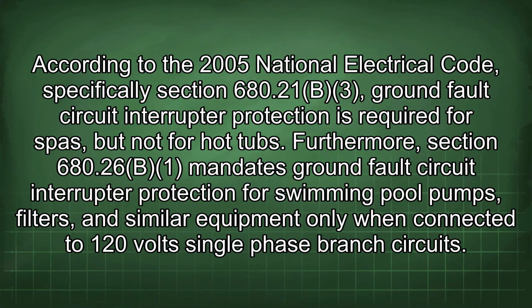According to the 2005 National Electrical Code, specifically Section 680.21(B)(3), ground fault circuit interrupter protection is required for spas, but not for hot tubs. Furthermore, Section 680.26(B) mandates ground fault circuit interrupter protection for swimming pool pumps, filters, and similar equipment only when connected to 120-volt single-phase branch circuits.